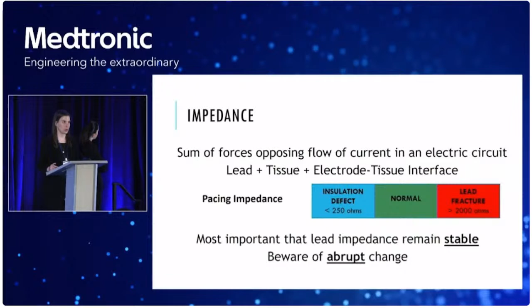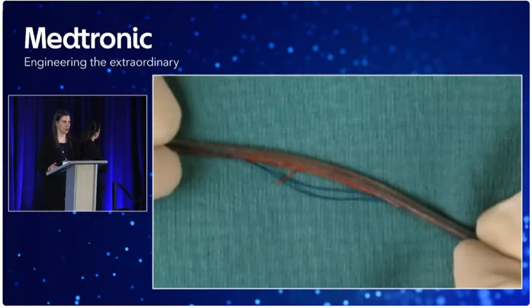So it's important to have a sense of what the trend has been for our impedance values, because we don't like sudden changes. And things like remote monitoring, which we'll talk about tomorrow, can be very helpful when looking for those warnings, those lead integrity alerts. And that's an example of a lead no longer in the body that had a breach in the insulation. So things you don't want to see that you might appreciate fluoroscopically, but it's nice when they're not in your hands after an explant. All right, we breezed through that. You've got it, I hope.